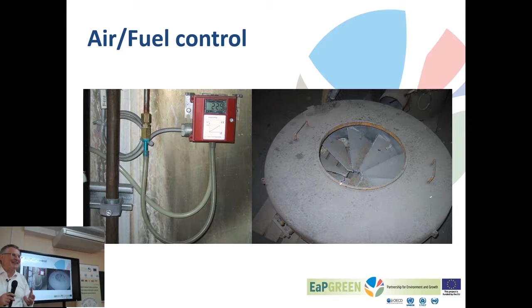Another example here, this is a hot water boiler. It's operating on natural gas. Water temperature is about 70 degrees. This here is the chimney, and this is a temperature indicator in the chimney. It has two scales, one in Fahrenheit and one in Celsius. And if we look at the indicator, we will recognize that the temperature reading is 250 degrees Celsius, which indicates that there is something wrong, because this temperature is much too high.